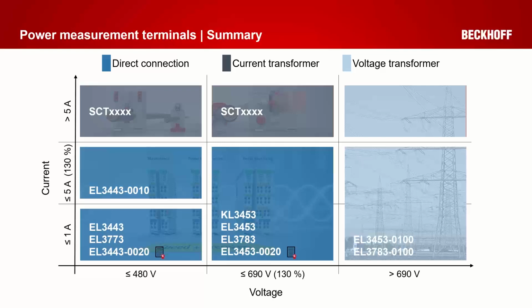Coming to the voltage range and current range, this diagram overviews typical applications with our terminals and the voltage and current ranges. On the x-axis, we have the different voltage levels. We start first with the 400 volt low voltage, which is more typical for actuators like motors and pumps. Then we come to the 690 volt levels, which is typical for generator, converter, the main low voltage distribution, the wind turbine. And above 690 volts, we are coming to the medium voltage.